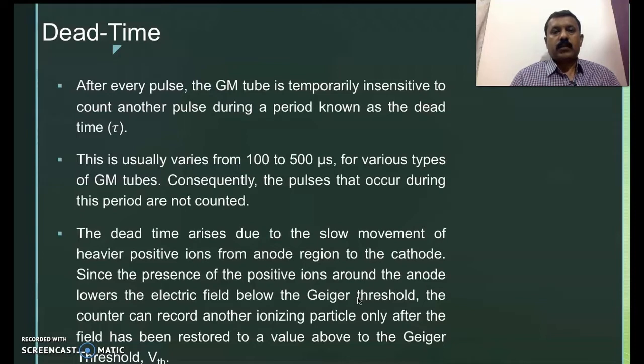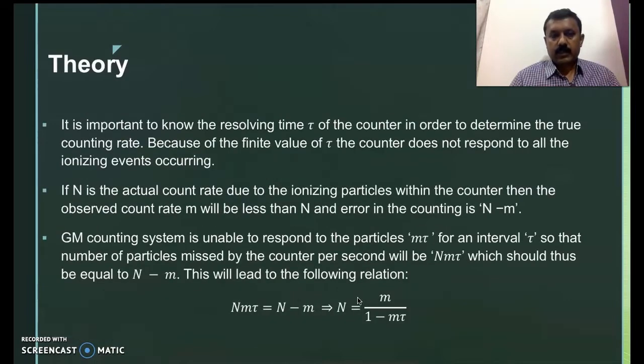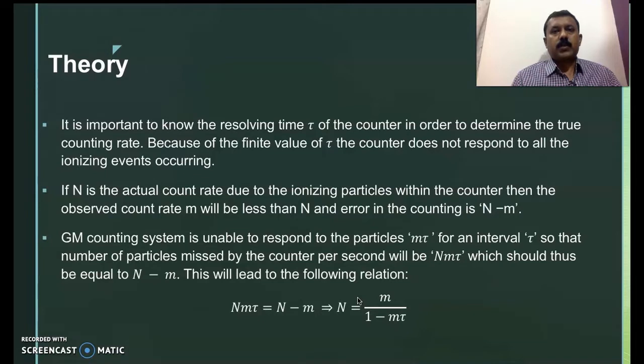If the voltage is below the Geiger threshold, then the GM counter becomes insensitive — it will not count. We have to wait till there is re-establishment of this threshold voltage. This time duration during which there is a decrease and then re-development of the threshold voltage is referred to as dead time of the GM counter. If the dead time is less, then the counter is more sensitive, and vice versa.